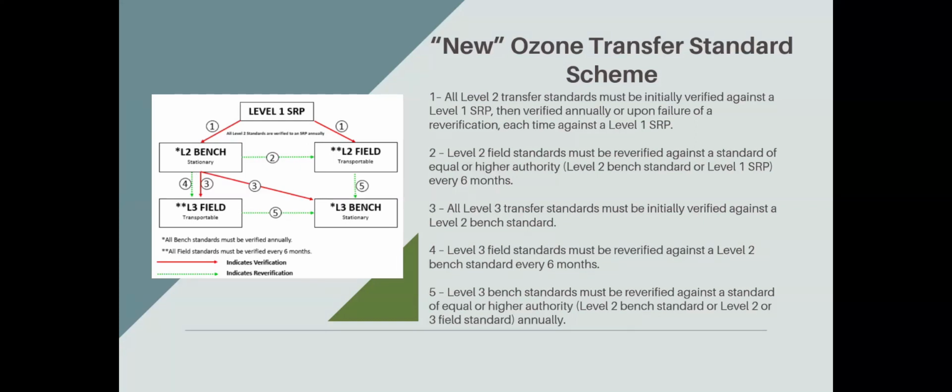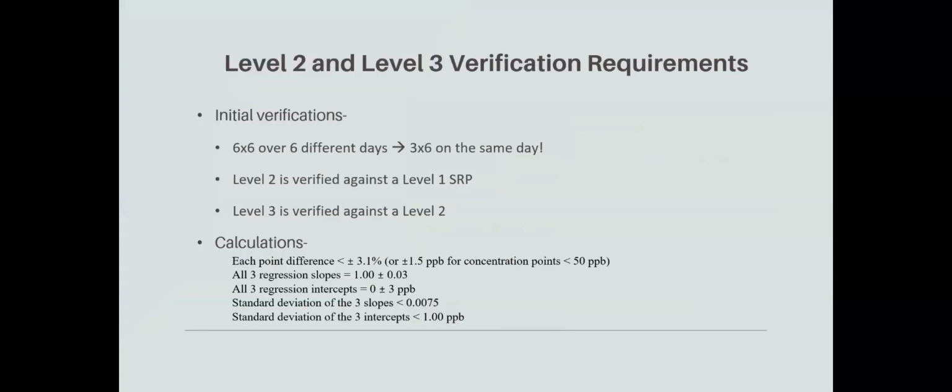Next, all level 3 field standards must be re-verified against a level 2 bench every 6 months. And then all level 3 bench standards must be re-verified annually, but that can be done against a level 2 bench or level 2 field or level 3 field. So, level 2, level 3 verification requirements.